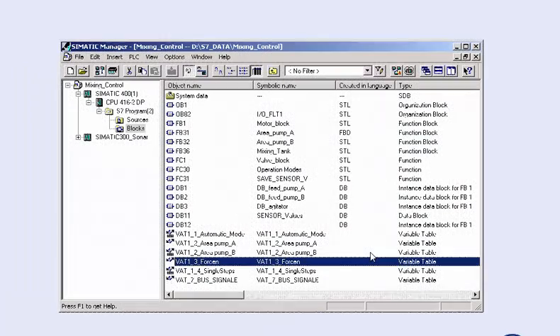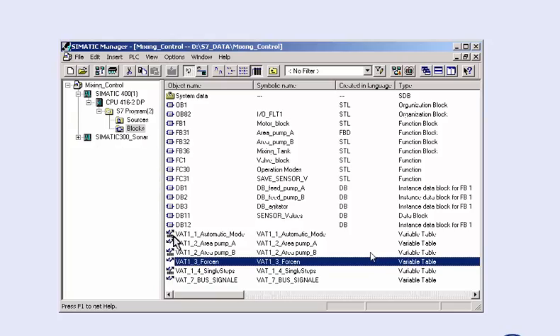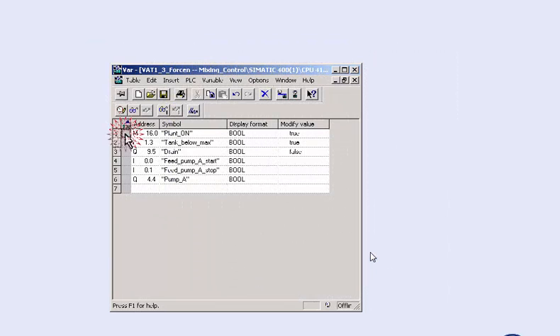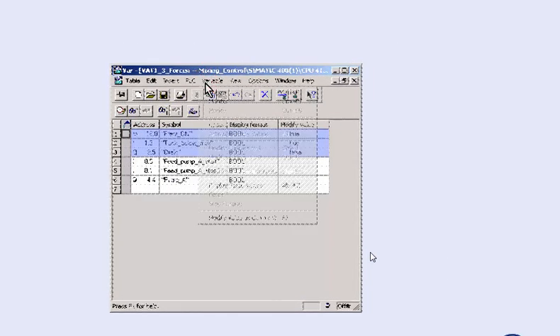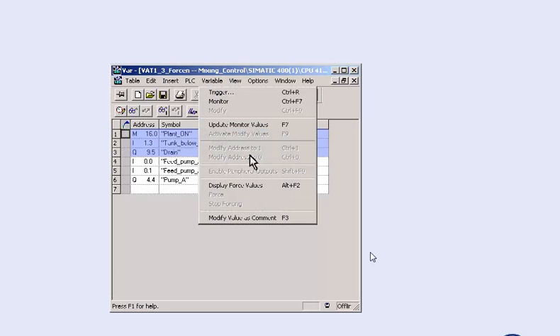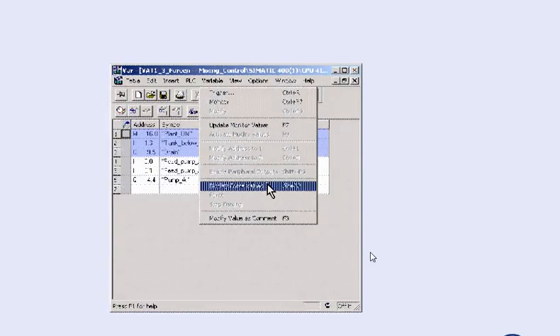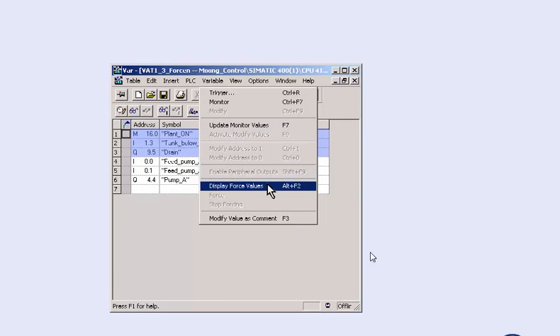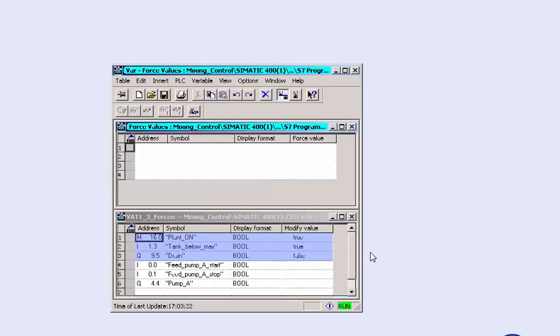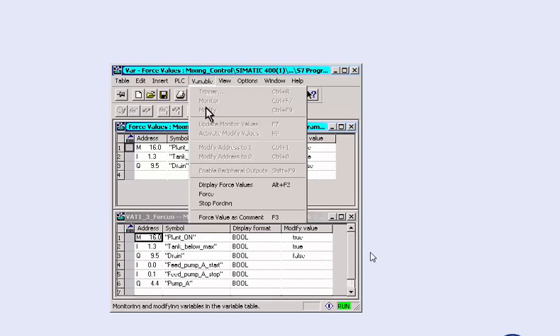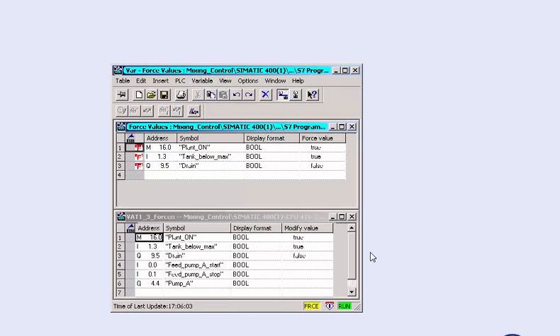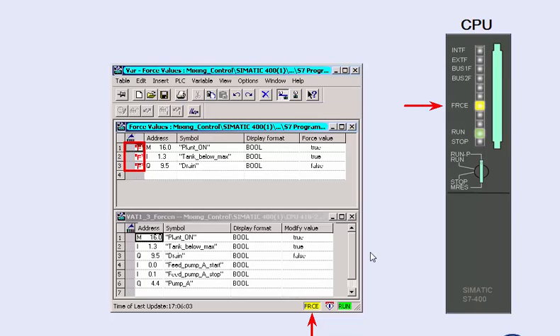In the project opened in the Simatic Manager, you select a predefined variable table and open it. You mark the parameters to be transferred to the force table. The menu command display force values displays the force table valid for the CPU and the selected variables are immediately transferred to the table with their control values. After activation, the CPU permanently executes the force job and indicates this at the respective operand as a force symbol. The status bar contains an indicator for the activated force operation, but the CPU also indicates this operating mode via a force LED.